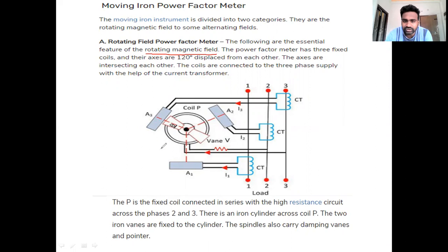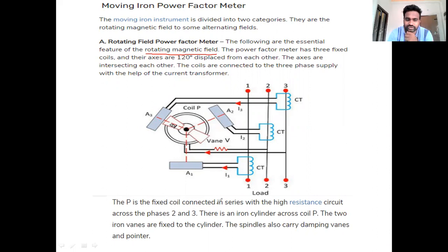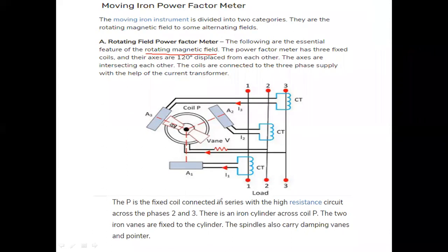Whenever three-phase supply is given to the fields A1, A2, A3, these three fields create a magnetic field at a phase displacement of 120 degrees. Analyzing the construction of rotating field type moving iron power factor meter: this type contains three coils — A1, A2, A3 — which are supplied with respect to three-phase mains. Electrical energy is supplied from current transformers.